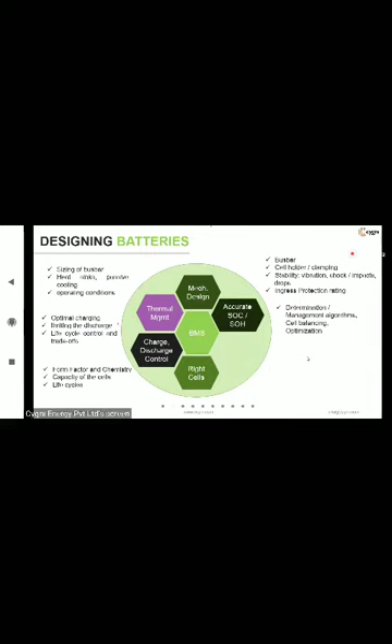Each cell may not discharge the same way at the same rate all the time. After a few months of operation, some cell may start deteriorating slowly. So there has to be a mechanism where balancing happens continuously, and that is one of the key factors a battery pack should have.